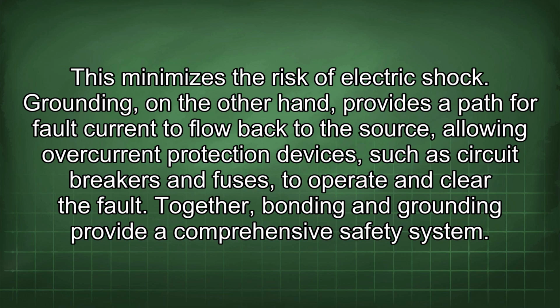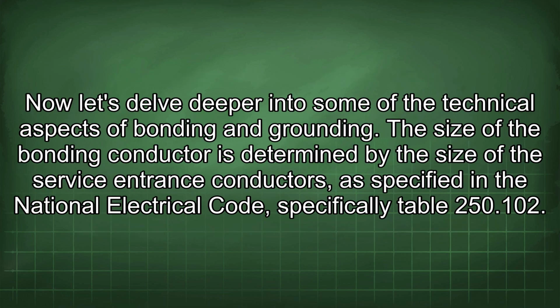Grounding, on the other hand, provides a path for fault current to flow back to the source, allowing overcurrent protection devices, such as circuit breakers and fuses, to operate and clear the fault. Together, bonding and grounding provide a comprehensive safety system. Now let's delve deeper into some of the technical aspects of bonding and grounding.